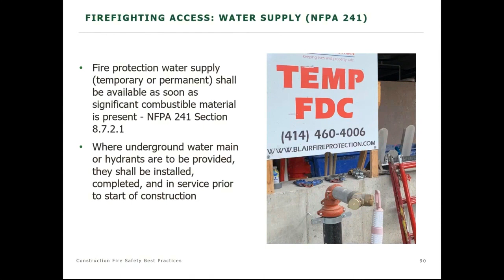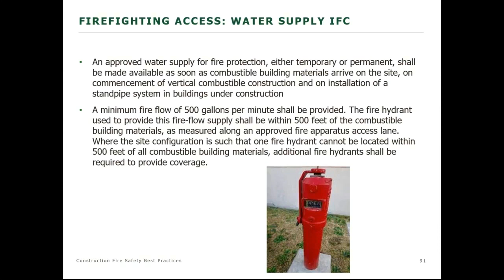Now, the IFC, just recently in the last edition, provided some fire flow requirements. Part of it is based on the proximity to adjacent structures. So if you are within 30 feet of an adjacent lot line or a structure, you have to have 100% of the fire flow of the completed building or 500 gallons per minute, whichever is greater. If it's 30 to 60 feet, it's half of the fire flow of the completed building or 500 gallons a minute, whichever is greater. And if it's more than 60 feet, you just have to have 500 gallons a minute. So it gives you a little bit of guidance. Now, is 500 gallons a minute adequate? This one local interpretation says you have to have 1,500 gallons a minute. This is a local interpretation I plucked off the internet.